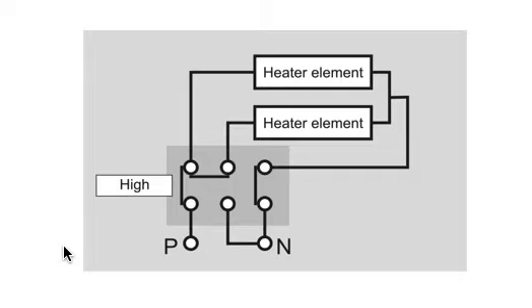In the final position, in the high position, our controller connects this phase coming in to both of the heating elements. And so the phase is fed to element 1 and 2 and the back end of the elements go via this contact to the neutral.